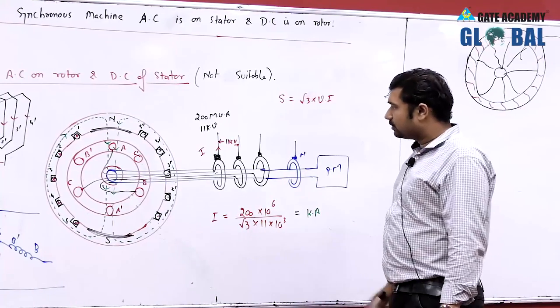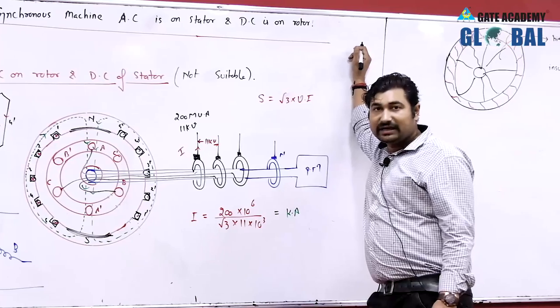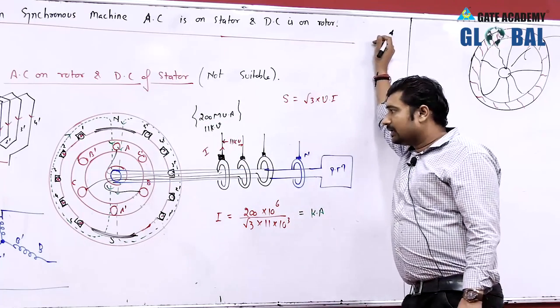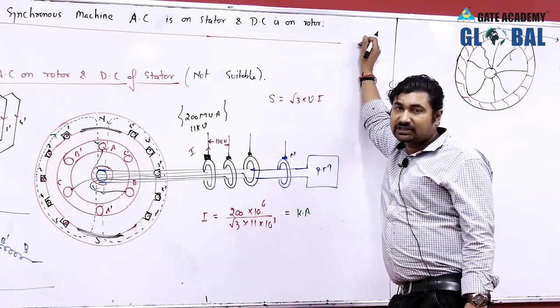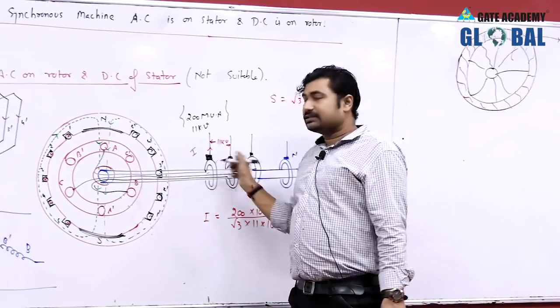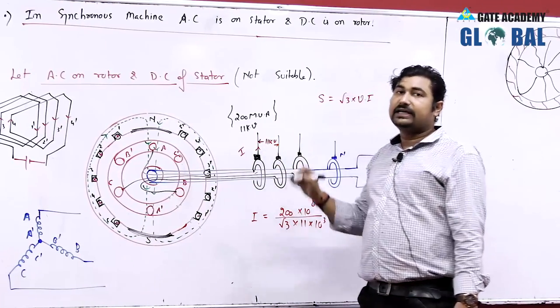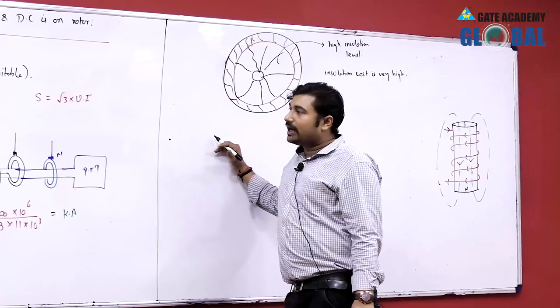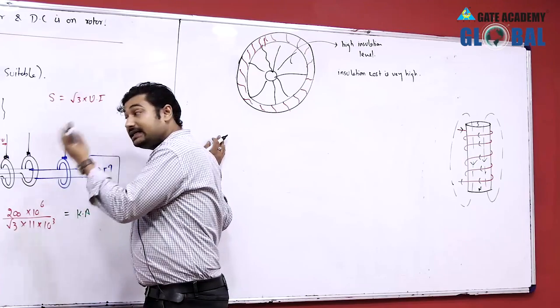Because of very high current flowing through the slip rings, the brushes require very frequent maintenance. A large 200 MVA generator — mostly used in thermal power plants — takes 15 days to start. We cannot stop the plant every 10-15 days to replace brushes. These brushes get damaged continuously as the rotor rotates and high AC current flows through them. To avoid frequent maintenance of slip rings, we prefer AC on the stator and DC on the rotor field.